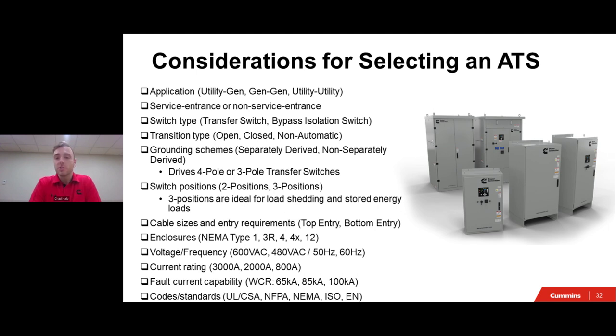So if you're in emergency, do you need that center off position for delays or anything else? Because if so, then you'll need that three position switch, or maybe you don't need the center off and then you'll have to go with that two position switch. And then also, do you need to communicate with the utility and put in extra safeguards if you are providing a closed transition? So being able to think about all those things and understand that if you're choosing a closed transition type or a time delayed transition type, there are extra steps and things that need to be taken into consideration when applying your automatic transfer switch into an application. And once again, do you need to be looking at getting into a three position transfer switch if you're using an open transition?